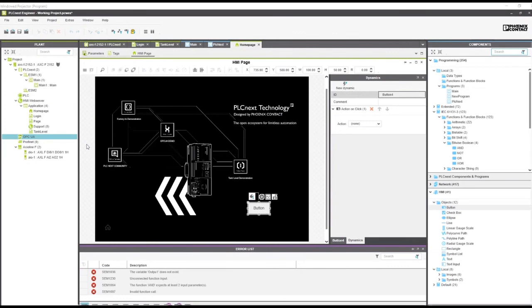You can install a third-party process like Node-RED, and you can have an OPCUA node which connects to an MQTT broker and publishes it to that server, so that you can have that instantaneous interaction with the PLC.